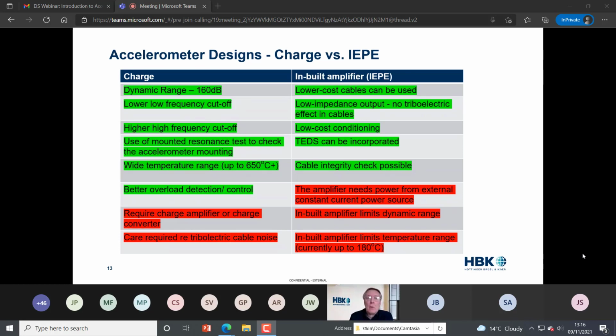160 dB is really wide. But the downside of the charge output type is that you need a charge amplifier or converter, and you have to be aware of something called triboelectric noise, which is all about movement in the accelerometer cable.